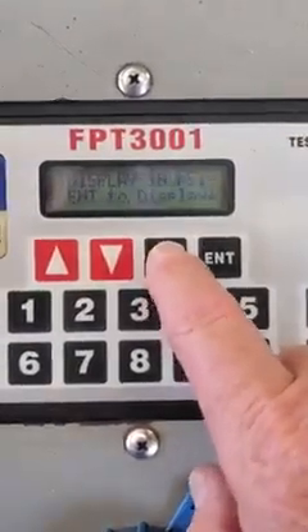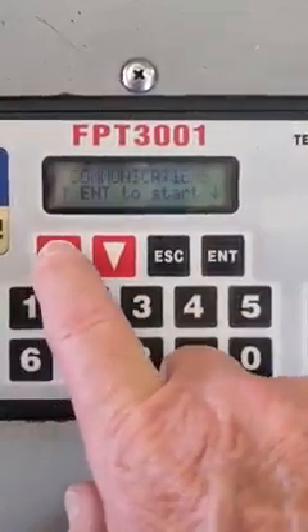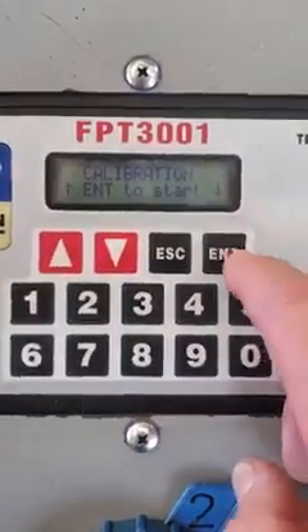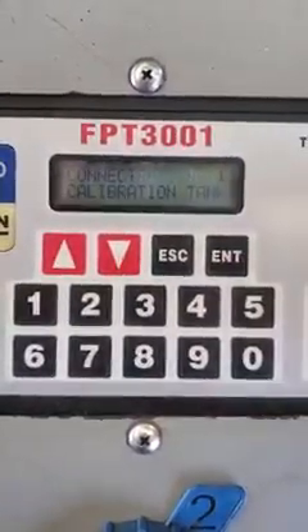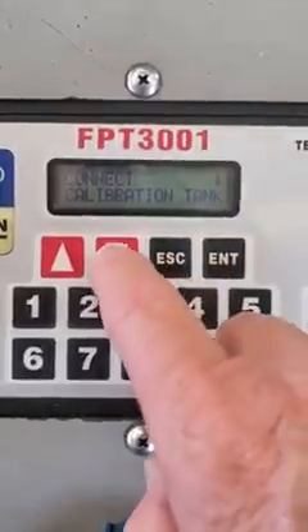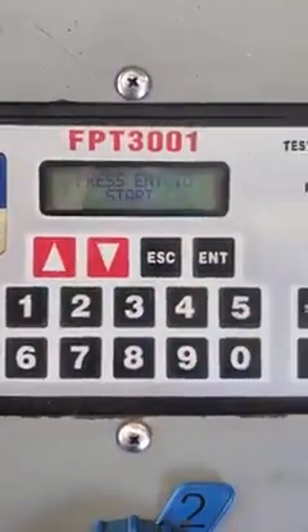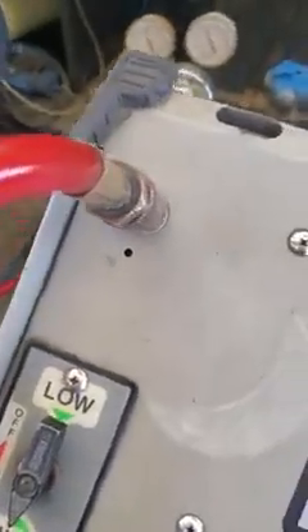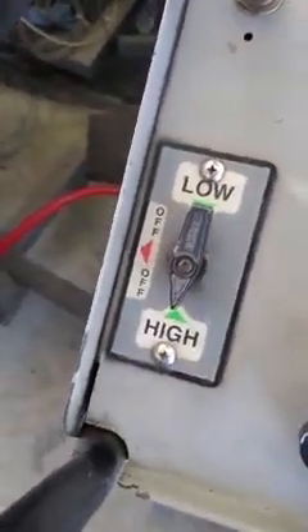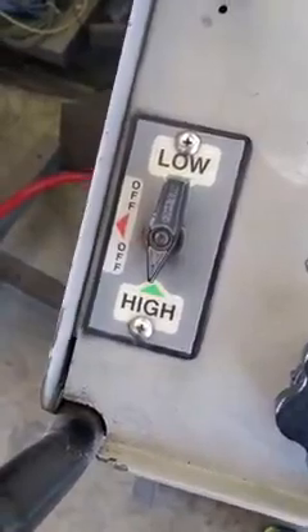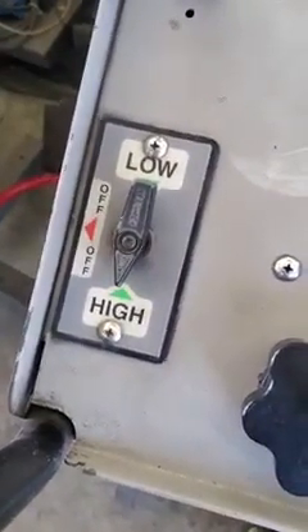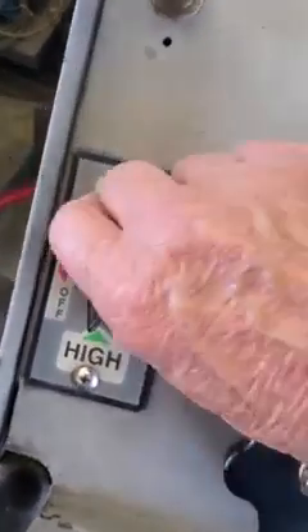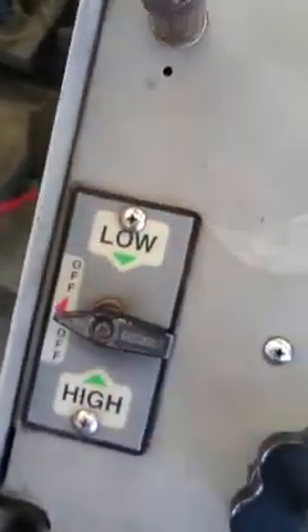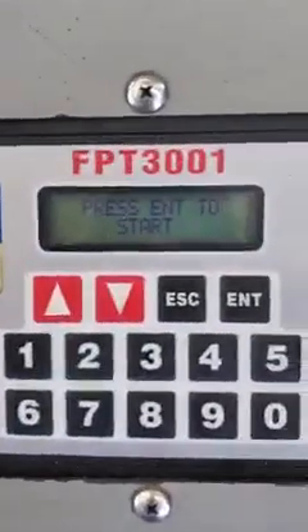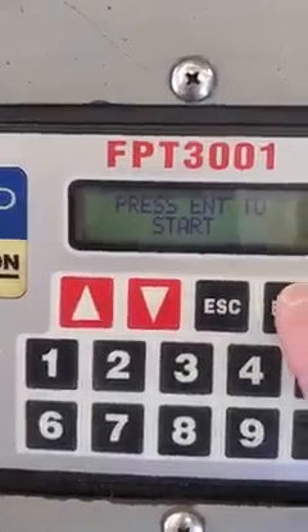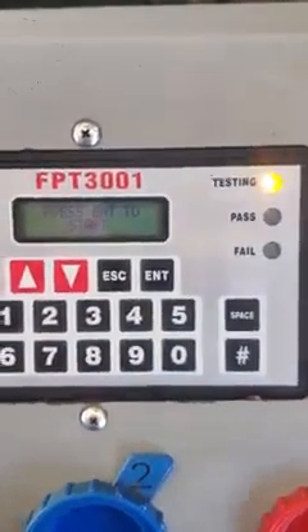So escape, escape, scroll up to calibration, push enter, down, down, and of course your red hose is connected and your high-low valve is set to high, so your calibration tank can breathe. Turn your valve to off and push enter to start the calibration.